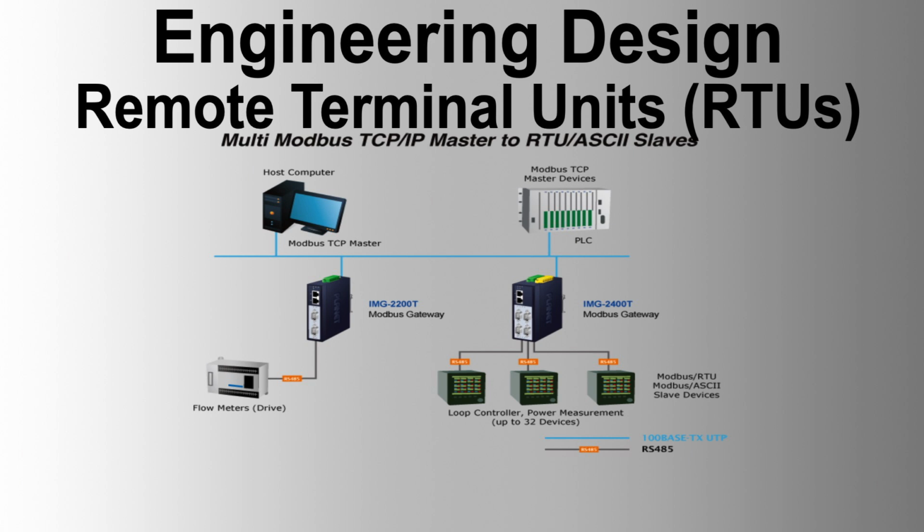1. Self-contained units. RTUs are designed to be self-contained, capable of collecting and processing data from intelligent devices such as ESD PLCs and VSD systems through Ethernet and serial interfaces. They also interface with third-party systems like metering systems via dry contacts, current or voltage signals, and contact-making pulsing devices. 2. Power management. RTUs ensure no false outputs occur during power up or power down and support a minimum of 256 unique RTU addresses. Selection interlock features prohibit more than one control selection at a time.